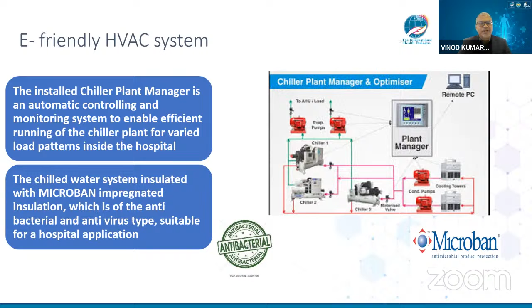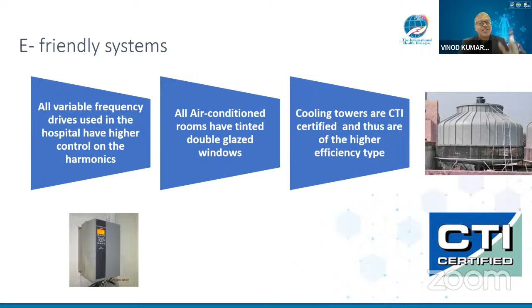Other methods are variable frequency drives, which I mentioned, double glazed windows, tinted windows for all the air-conditioned rooms, and cooling towers. See, the cooling tower is the machine which is dissipating the building's heat into the atmosphere. If it is inefficient, your air conditioning system is inefficient, and when that happens your electricity bills go up. So you need to see that when you buy your cooling towers, they are CTI certified, Cooling Technology Institute, the American-based institute. That makes it very reliable in terms of heat dissipation and energy efficiency as well.